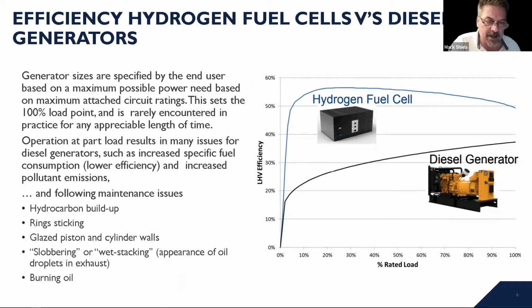So the issue that you have with diesel generators is that at part load, its operation is really suboptimal, and this results in many issues for the diesel generator itself. In addition to an increased fuel consumption because I'm operating at lower efficiency, that can result in increased pollutant emissions. Operating diesel generators at any kind of part load generally has the issues mentioned at the bottom, like the development of hydrocarbons, sticking rings, I can start damaging the pistons, glazing the cylinder walls, I can create a wet stacking type environment, and I can also end up burning more oil. So basically DGs are normally sized for peak demand, but the basic problem in most situations is they're normally run at part load, which is usually the brunt of most of the problems.